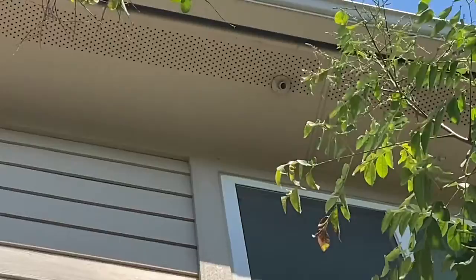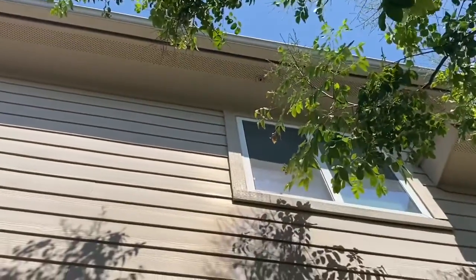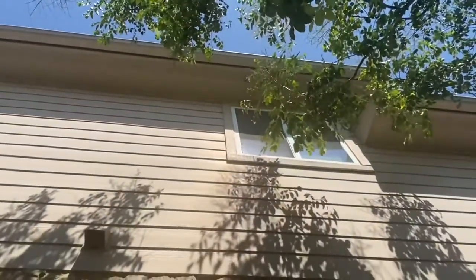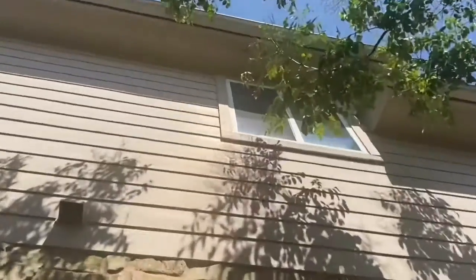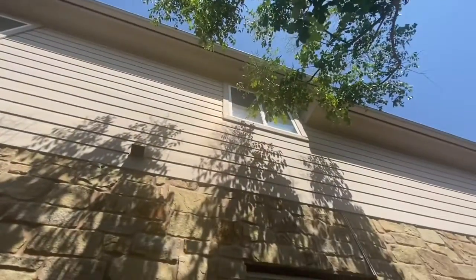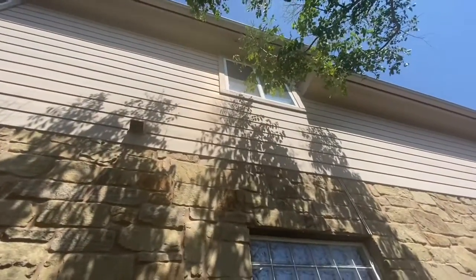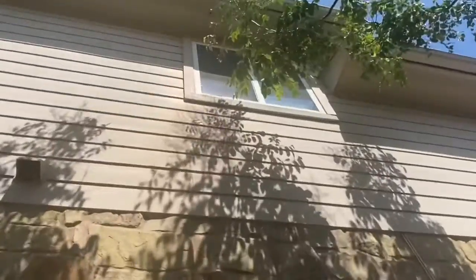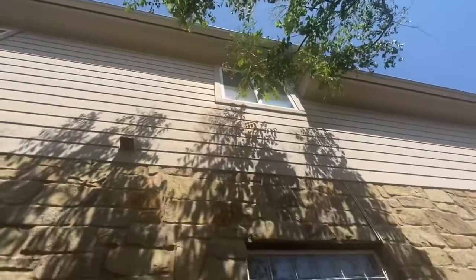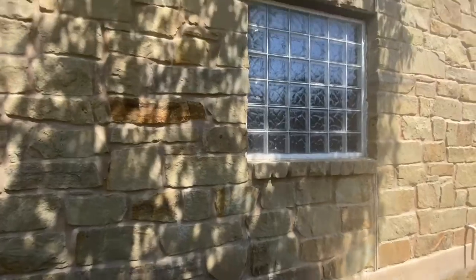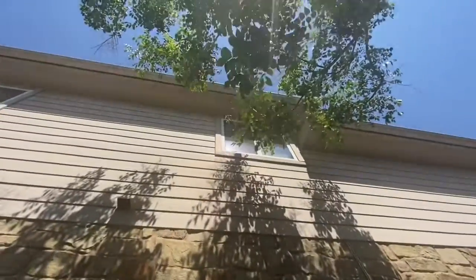I did not know that that's an overflow line for a long time, and I started noticing that the water was dripping from there for almost a year. I didn't even realize that there was an overflow going on. I thought that's normal, and I was even planning to see how to harness that water, because I always see a small puddle of water here from the water that's flowing from the overflow line. So today we are going to see why this overflow occurs and how to fix it.